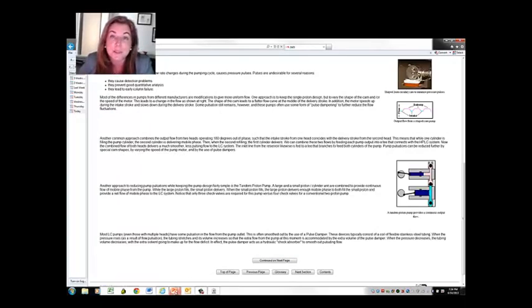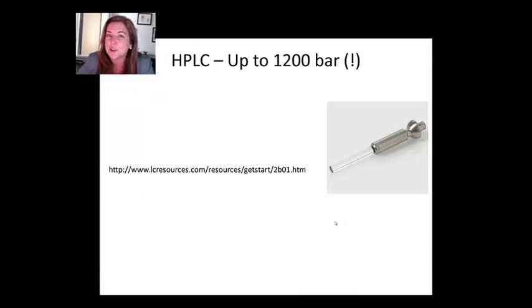So I hope that that pump discussion was kind of interesting. It's not generally something that we think about when we are using an HPLC as chemists. But a lot of times if you're troubleshooting problems in an HPLC, it's surprising how frequently those problems arise in the pumping system. You have to take it apart and put it back together. So having at least some idea of what it looks like can be useful.